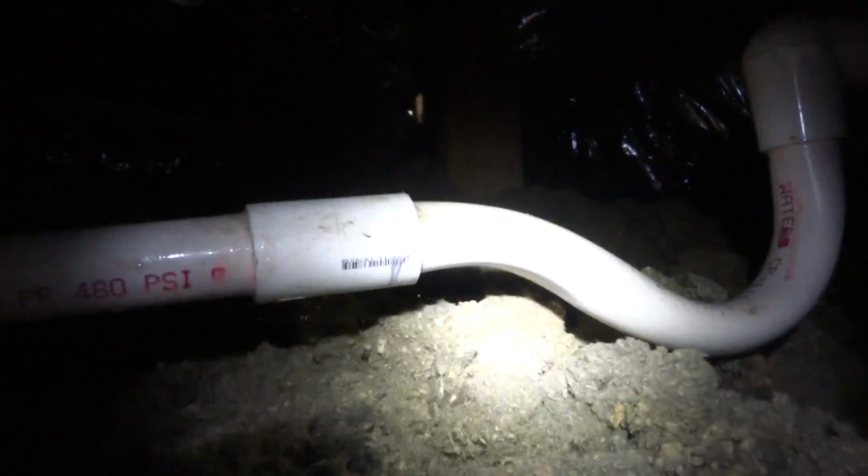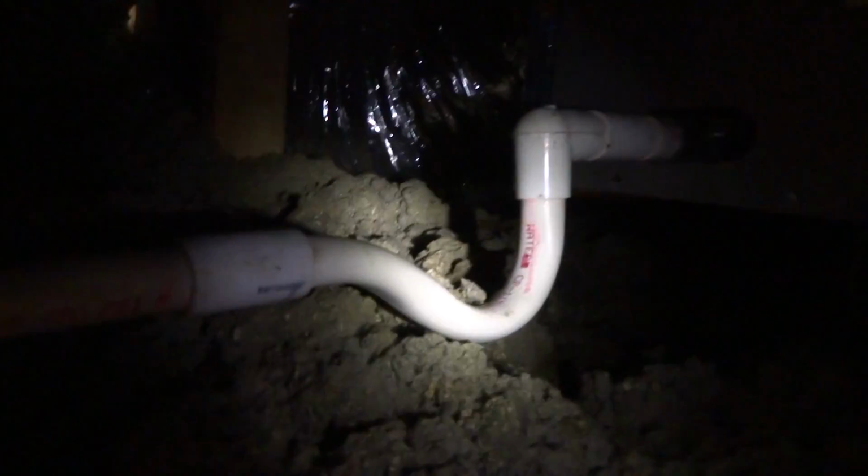That's kind of a shoddy job. I mean, I could probably put one secondary pan on it. It's blocked. I could put a float switch on there, but it really should have a secondary pan under this thing. Kind of a poor setup here. But it's flowing, it goes right out. I think I told him last time I was here it needs a secondary pan under it. I think I got one that would fit right in here too. So there's nothing light over there. Filter looks clean.